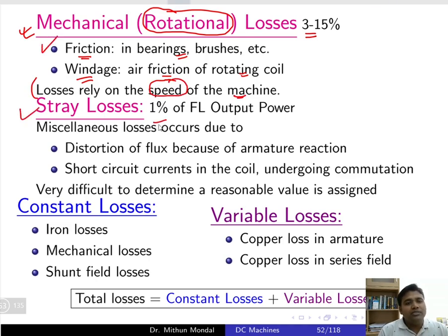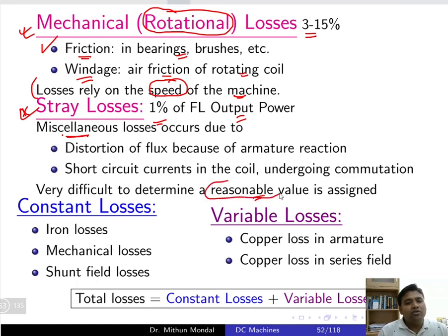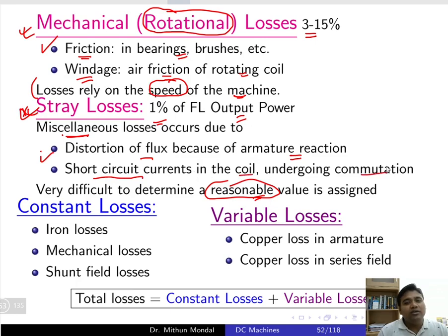Stray losses are around 1 percent of the full load output power. They are generally neglected as they are miscellaneous losses which are very difficult to calculate to a reasonable value. Stray losses are due to distortion of flux because of armature reaction and short circuit current in the coil undergoing commutation — essentially caused by flux distortion or short circuit current.